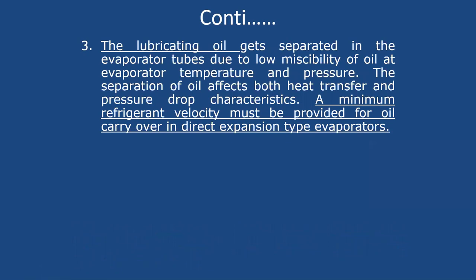The lubricating oil, so deposition of lubricating oil in the evaporator coil, is again a main concern as far as maintenance is concerned, because most of the lubricating oil is not miscible with the refrigerant. So what happens there? As the refrigerant evaporates, it converts into vapor, but lubricating oil deposits there. The separation of oil affects both heat transfer and pressure drop characteristics, because if the oil deposits, it obstructs the rate of heat transfer. Minimum refrigerant velocity must be provided for oil carryover in DX type evaporators, because if the oil deposits there, there is a shortage of oil in the compressor, and in due course of time, a failure of the compressor may happen.